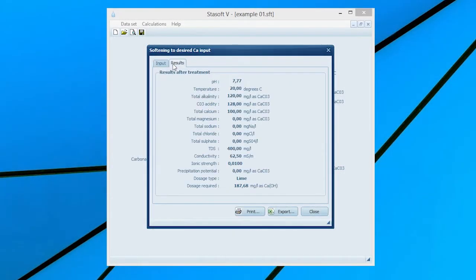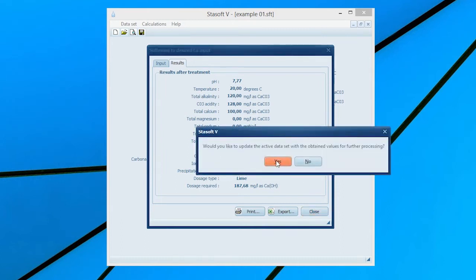Selecting the Results menu option will bring the Results After Treatment window onto the screen with values for the new state of the water and the dosage of lime required to soften the water to the prescribed calcium concentration. Selecting the Close option allows the user to update the active data set with the present water's characteristics for future processing in the Update Data Set window.